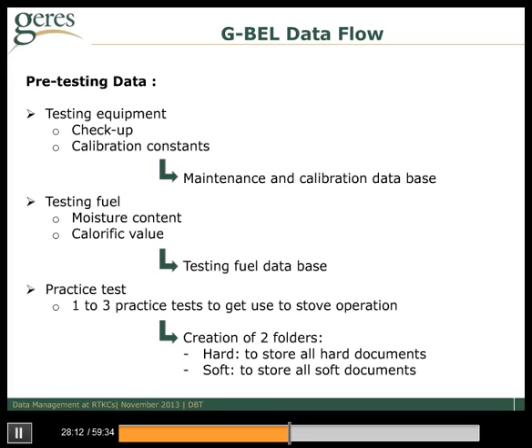So pre-testing data is the data needed to prepare the test. It includes data on testing equipment, such as the checkup of the good state of operation of the equipment. This is the case for equipment we can't calibrate in-house. For example, we are performing two-point testing of thermometers at 0 degrees C and 100 degrees C. When possible, we are performing calibration as we do for scale, and soon the determination of calibration constant for emission measurement equipment.